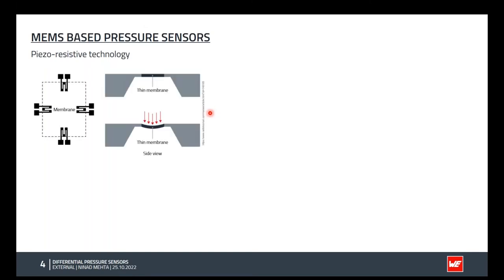Moving ahead, we talk about MEMS-based pressure sensors. Here there are different kinds of MEMS technology available in pressure sensors, namely piezo-resistive technology or capacitive technology. For differential pressure sensors, piezo-resistive technology is more popular, so we are going to focus on the piezo-resistive technology. This is based on piezo-resistivity, where the resistivity of the material changes when the material is under stress or any force or pressure.